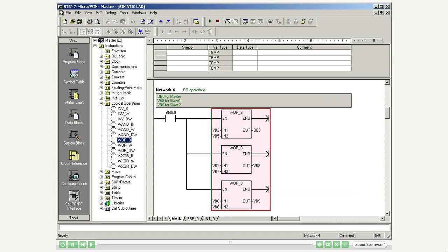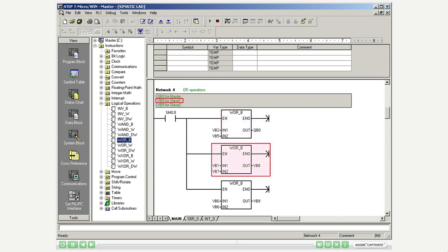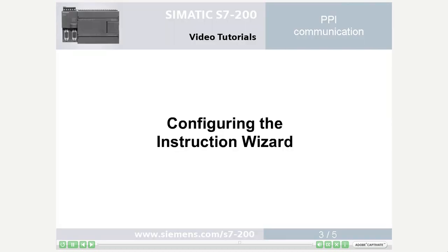The byte by byte logic OR connections of rising and falling running lights per PLC occur in NetW4. For the master the result is directly output at QB0, and for the slaves it is intermediately stored in V memory byte 8 or byte 9. Step 3: configuring the instruction wizard.